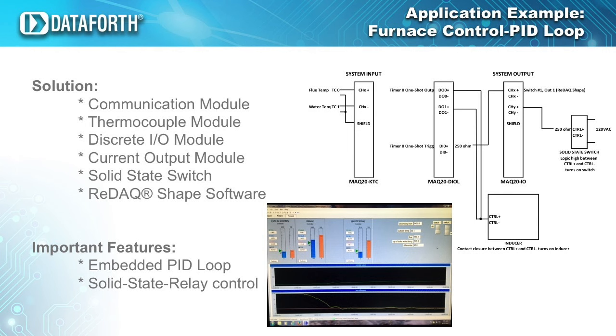First off, the developer found the hardware, system configuration process, and ReDAQ Shape software all intuitive and easy to install and operate. Next, the hardware and software allow simultaneous operation of multiple PID controllers, some sharing the same input. Multiple trend charts can be displayed on the same view page, allowing the user to make controller changes and watch for resultant trends on one screen. While this may seem like a simple and essential feature, many industry-leading standard multi-loop controllers do not offer this.